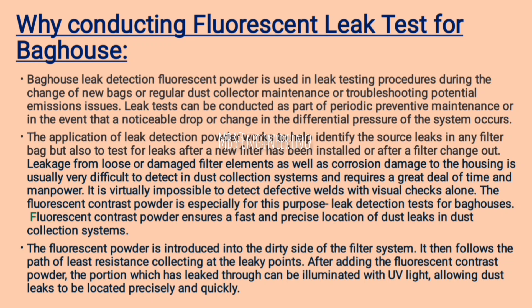The application of leak detection powder works to help identify the source of leaks in any filter bag, and also to test for leaks after a new filter has been installed. After a filter change-out, leakage from loose or damaged filter elements as well as corrosion damage to the housing is usually very difficult to detect in dust collection systems and requires a great deal of time and manpower. It is virtually impossible to detect defective welds with visual checks alone.